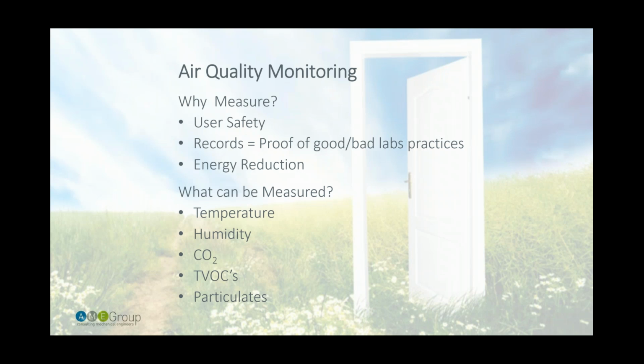And with the Aircuity system, it takes measurements in each lab about every 10 to 15 minutes. And so it's just not quick enough to be the source for that alarming. And so we've got separate sensors in those labs that are specifically measuring the levels of hydrogen in those labs. So just be careful when you're looking at different chemicals and what's being used and what you can rely on the system to measure.